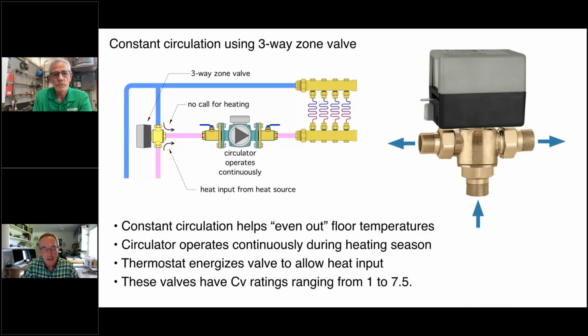And the reason we like it is typically you get those cold spots near those doors, either from air leaking under the door or just a lack of insulation, a thermal break between the inside slab and the concrete ramp outside. And with constant circulation, you're basically grabbing BTUs that are in the core of the slab, farther inside the building, and you're relocating them near these doors. So it kind of evens out that floor temperature.